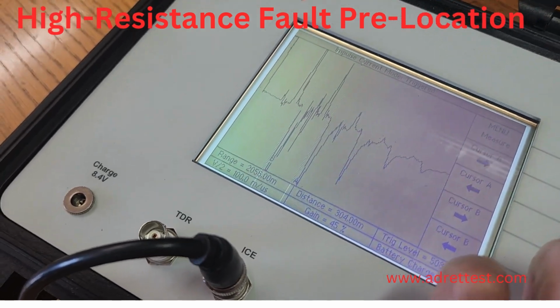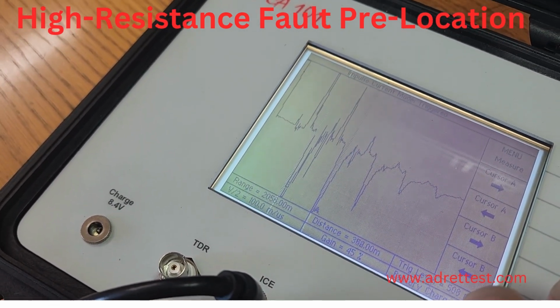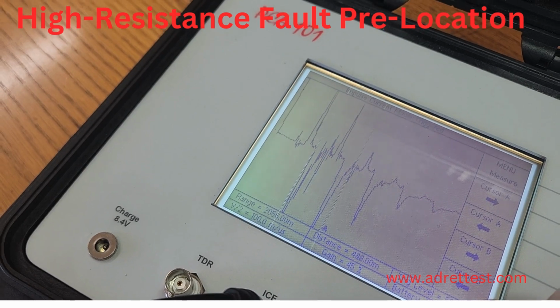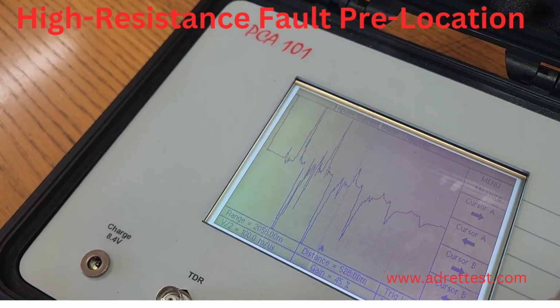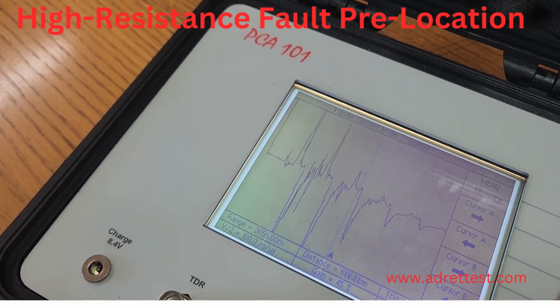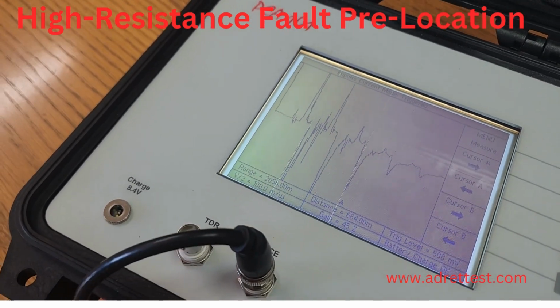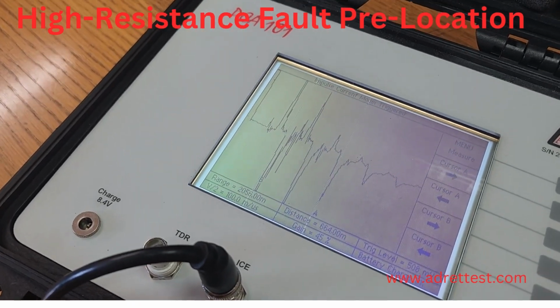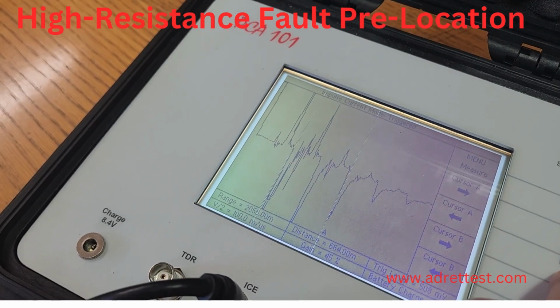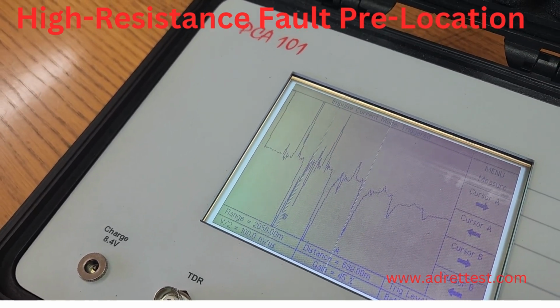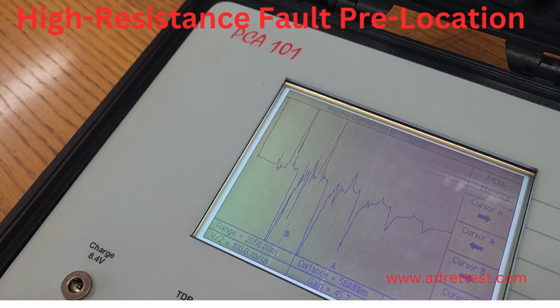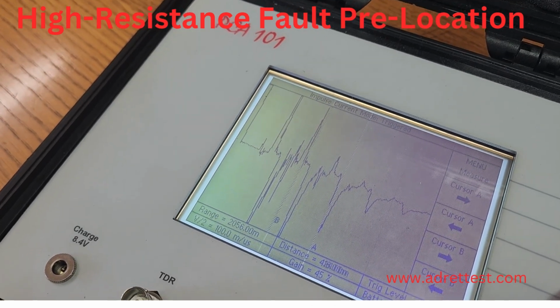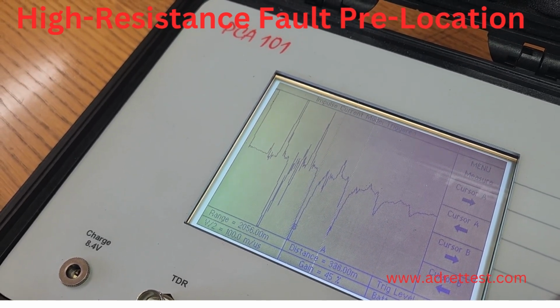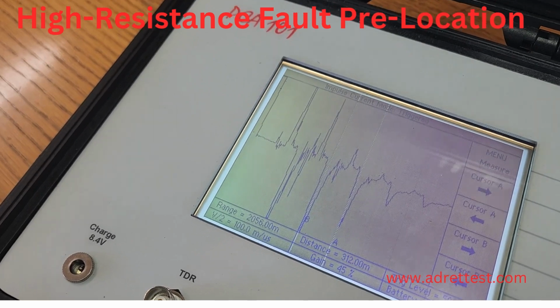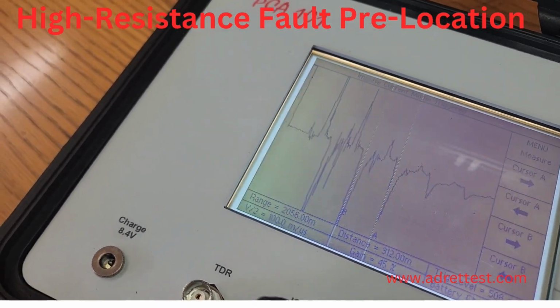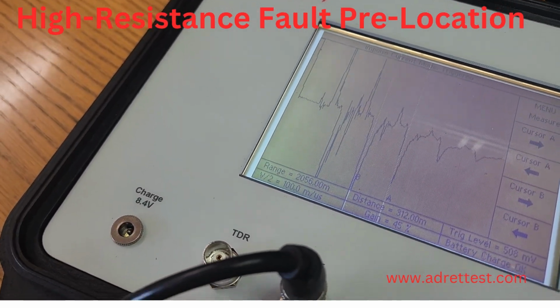Depending on how you move it, if you move it roughly, you would see that it sometimes will be 30 meters over the fault. This is because of all the wiring and stuff in the surge generator, so you can just deduct that. If we measure from lower peak to lower peak on our next one, there you can also see there's our approximately 300 meters. It'll put you in the vicinity of the fault.